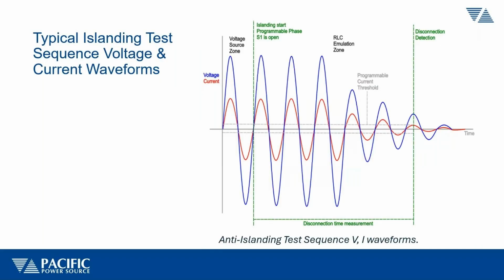This is what an anti-islanding test would look like if you looked at one phase. You would be running normal operation. At some point, you would disconnect the output of the grid simulator, so the output would go away. At that point, the voltage and the current will still continue in the RLC circuit, fed by the DER. But the DER has to be able to detect that this condition occurred. Generally, when the grid disappears, and the grid is normally providing the synchronization of everything, these DERs will start wandering, frequently deviating. The voltage will start deviating because there are potentially one or more DERs connected, interacting with each other at that point. So when there's no longer a grid that keeps everybody in sync, they will start seeing deviations of the frequency and voltage, and they have to detect that quickly and respond accordingly by disengaging.